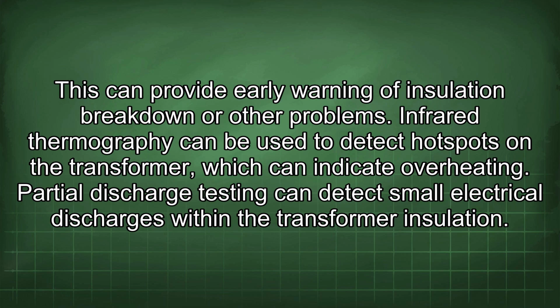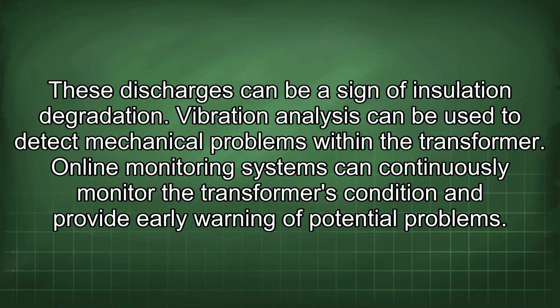Partial discharge testing can detect small electrical discharges within the transformer insulation. These discharges can be a sign of insulation degradation. Vibration analysis can be used to detect mechanical problems within the transformer. Online monitoring systems can continuously monitor the transformer's condition and provide early warning of potential problems.